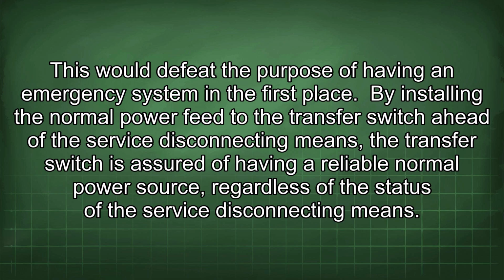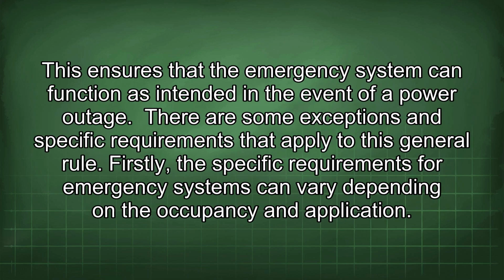By installing the normal power feed to the transfer switch ahead of the service disconnecting means, the transfer switch is assured of having a reliable normal power source, regardless of the status of the service disconnecting means. This ensures that the emergency system can function as intended in the event of a power outage.